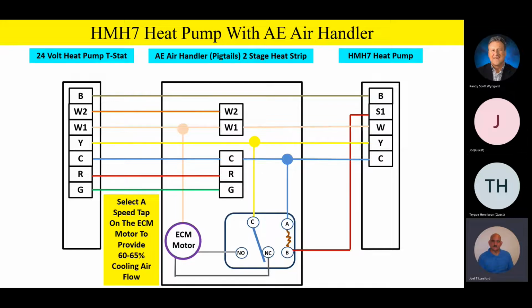So when we are in our lower airflow requirements, 35, 40, 45, 50%, whatever airflow, we're going to reduce that airflow. So the ECM motor needs to be blowing on reduced airflow between 60 and 65% of our cooling airflow. So as we hook this up, we see it's designed to let the outdoor unit make intelligent decisions based on its point of modulation and its point of capacity to reduce the airflow on the inside unit with that little switching relay. So as we take a look at that, again, there's our block diagram, how we're going to hook it up.